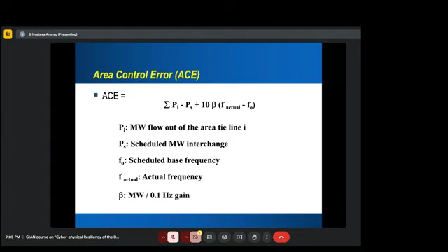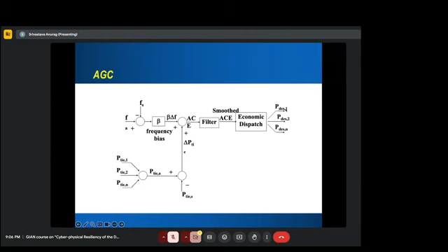Here's a pictorial view. You have the frequency difference, then frequency bias, which gives you B delta F. Then we have the tie line, tying two different areas or utility boundary regions, which gives us P tie. We know how much it should be, giving us delta P tie, and that's the ACE, or area control error. We can filter this to smooth out noise, then feed it to economic dispatch to find the dispatch for each generator - if we have 3 generation units, we find 3 P dispatch values; for n units, we do it for all n.